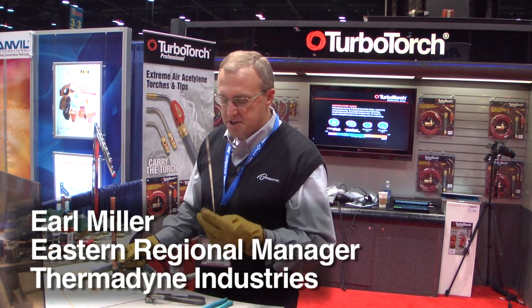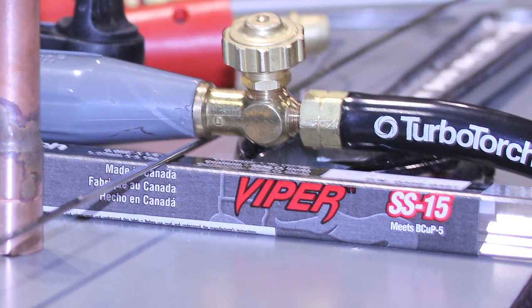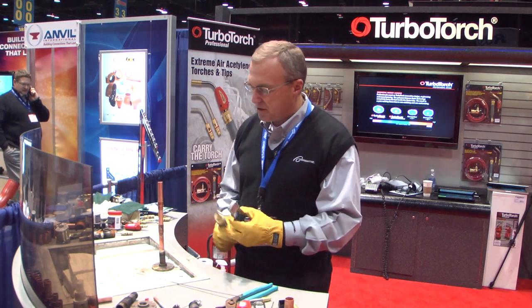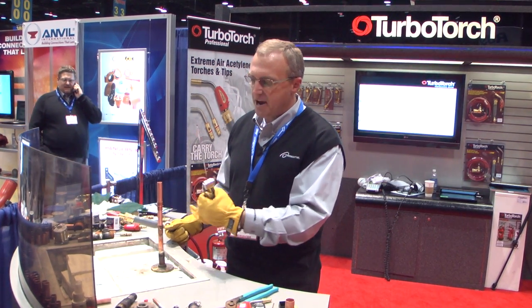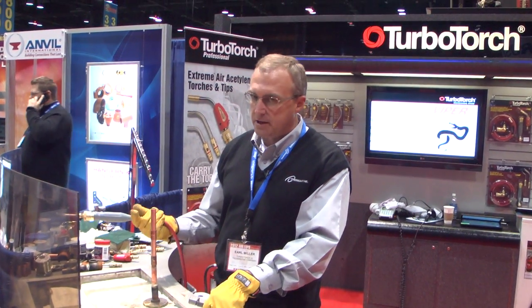The next process we're going to do is brazing — copper brazing — using a phos-copper rod. This has got silver in it; it's a 15% rod that's predominantly used in the HVAC industry. When you're brazing copper, this is for higher pressures. You have higher pressures going through ACR tubing and refrigerant lines, as opposed to plumbing lines when you solder.